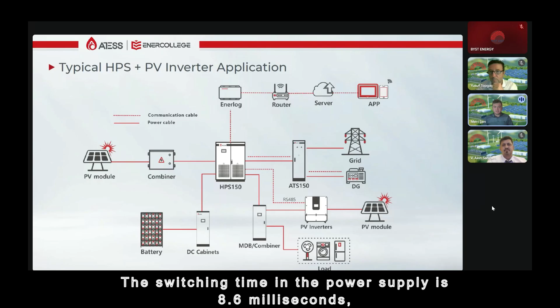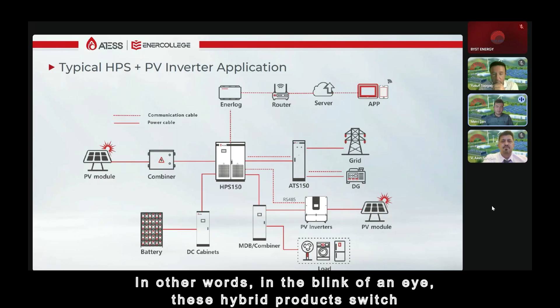You can also see this in our catalogs. The loading times are usually listed as 10 and 20 milliseconds. However, the critical loads recorded in the test documents are also accurate: the switching time in the power supply is 8.6 milliseconds, as recorded in the test documents. In other words, in the blink of an eye, these hybrid products switch over without any interruption, ensuring the end user experiences no downtime. This is the essence of an uninterruptible power supply, UPS.